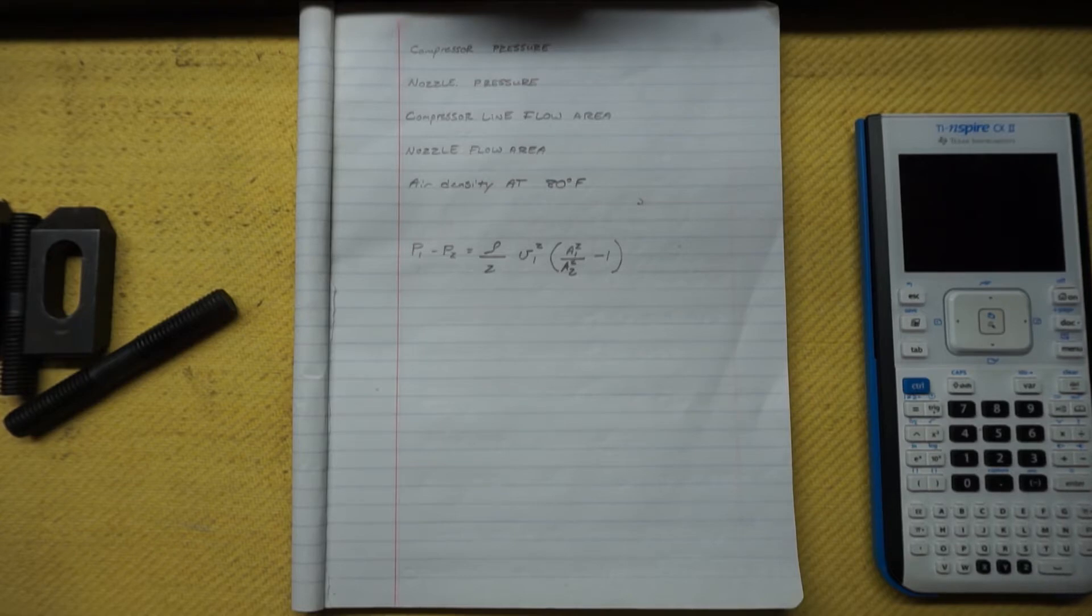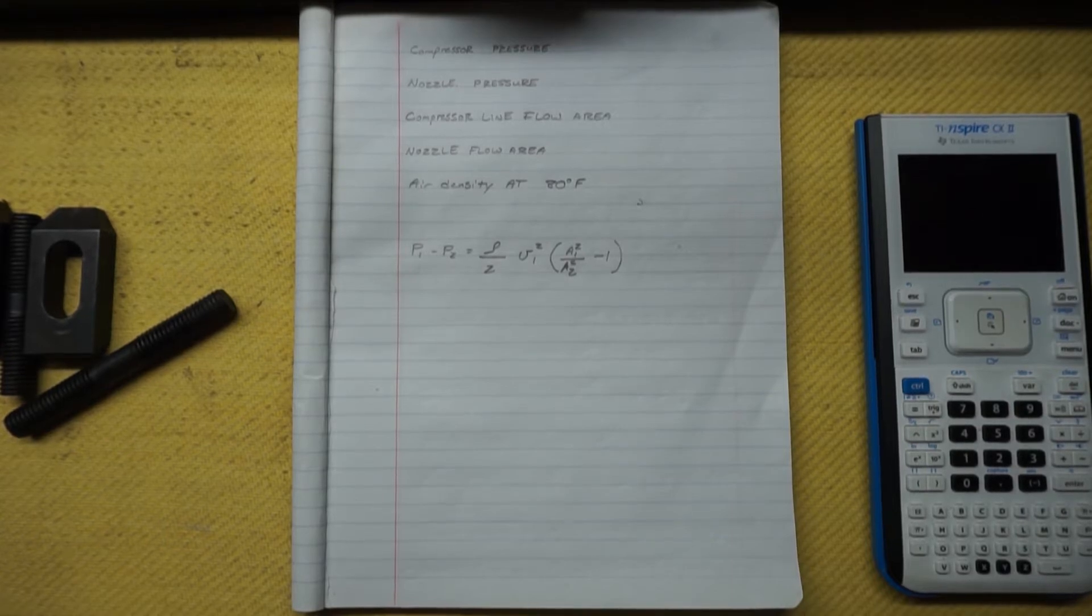Today's is going to be about an air compressor. A guy had come up to me, and then another guy, and then another guy in another shop, all asking well how do you know how big of an air compressor to get? Well that is based on your air supply requirements, what you want it to be. In this particular case, the guy had specifically wanted 130 PSI to be maintained at all times. So even if you were to break the line at the other end, which in his case was an air spray gun, if he were to use that for 20 minutes, he never wants to go below 130 PSI.